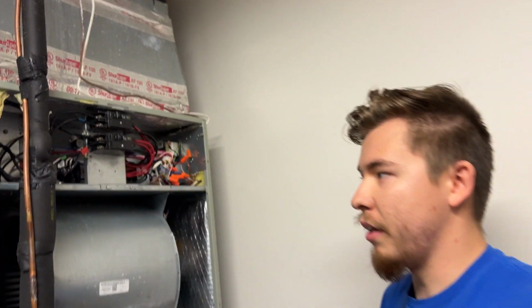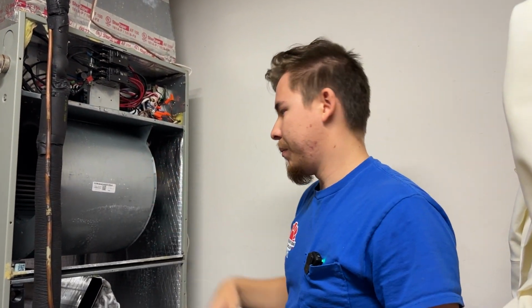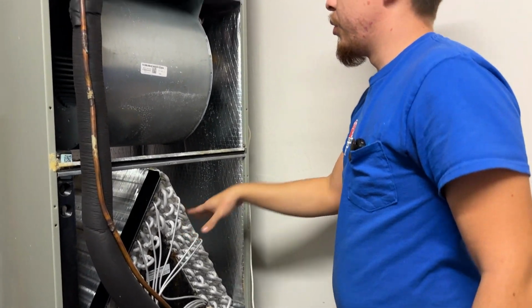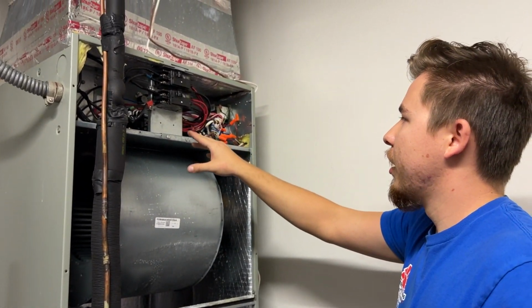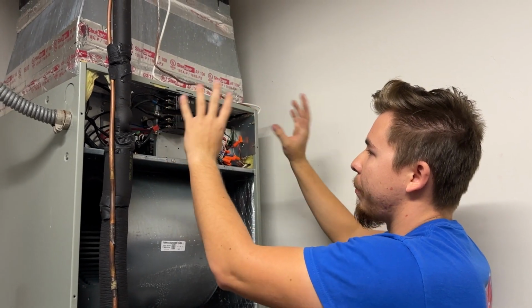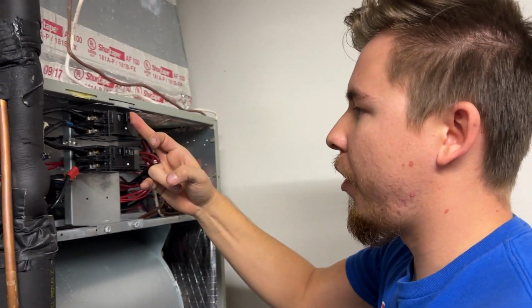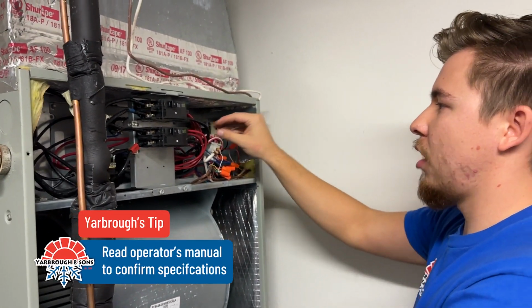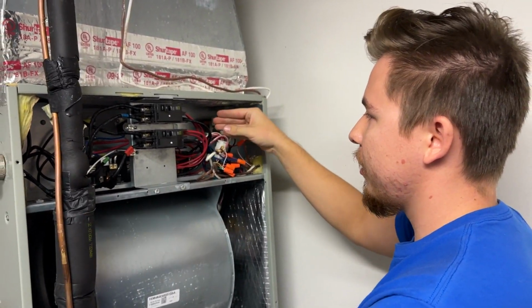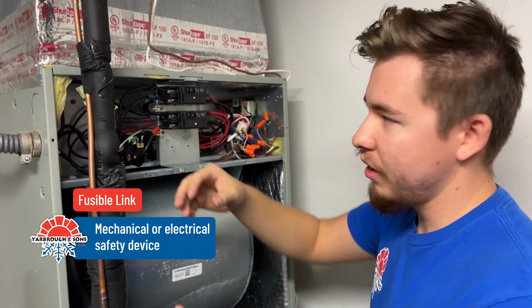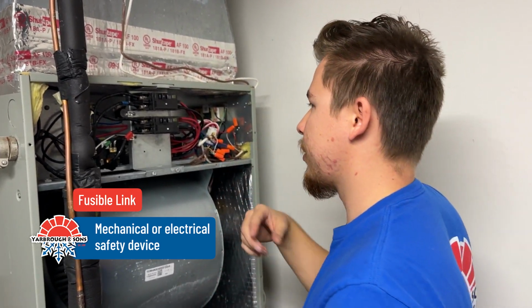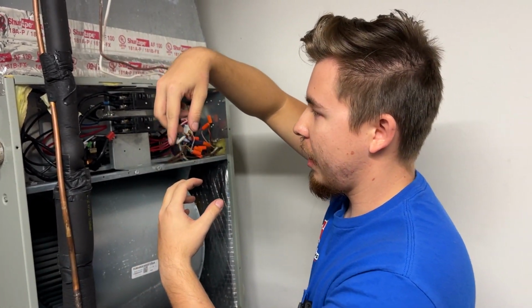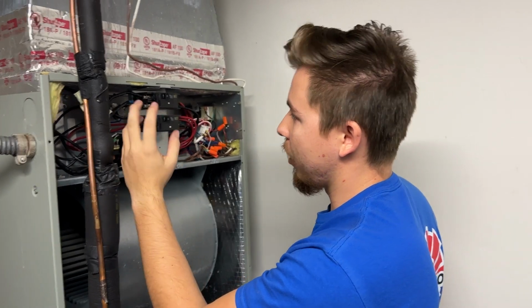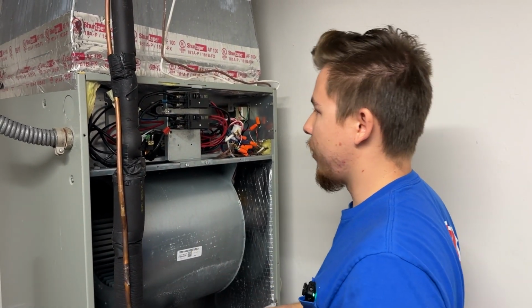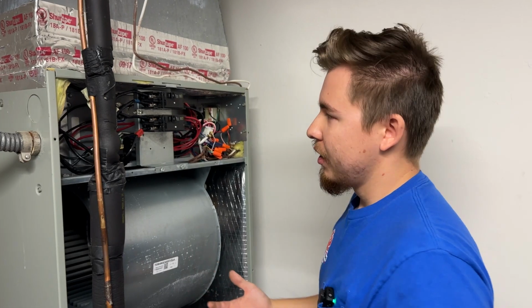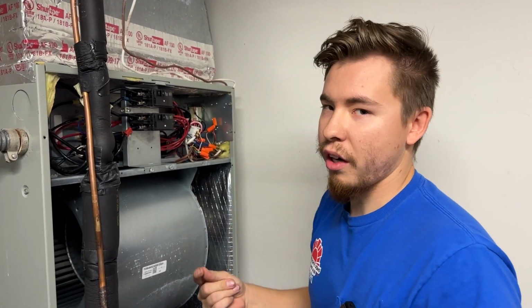It'll mostly either be straight AC or it'll be a heat pump. You've got your TXV, your evaporator coil, your blower, your breakers, and all these wires and stuff. Your heat strips are back behind it. How the heat strips work: it starts at your breaker, going to your fusible link. Your fusible link is what goes in your heat kit, which sends power to the other side of your heat strips. After that, your heat strip fusible link will go to a limit. What your limit does is determine if it gets too hot and something's out of whack, then it'll shut the unit off as a safety switch.